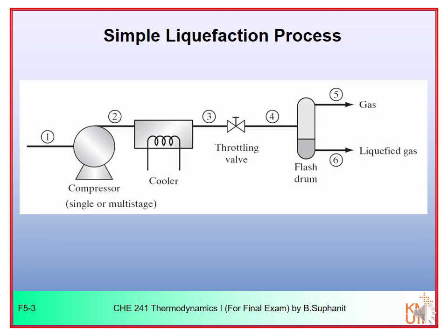The simple liquefaction process consists of three main steps. The first is compression — using a single stage or multi-stage compression. Normally we do multi-stage compression with intercooling, which requires much less work than a single compression step. Once compressed to high pressure, we cool the gas using a cooler.